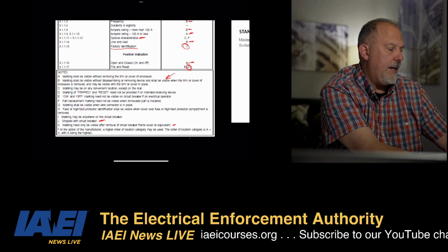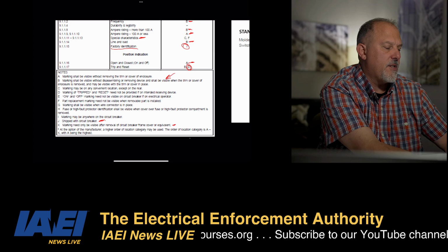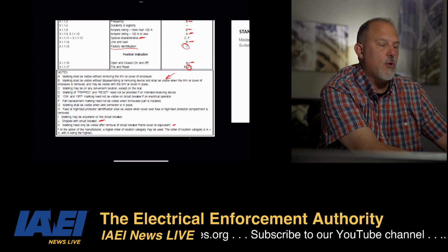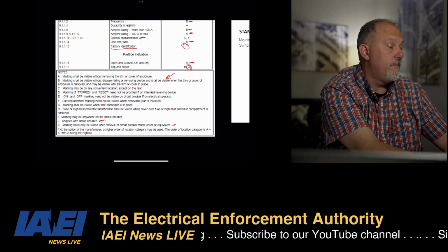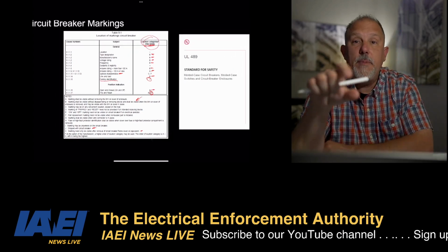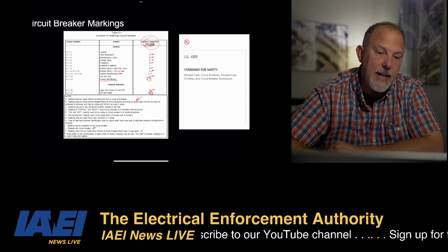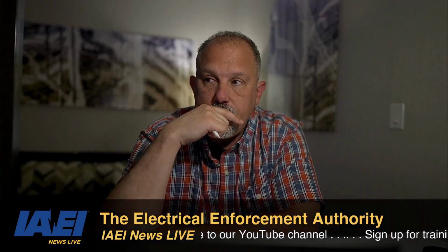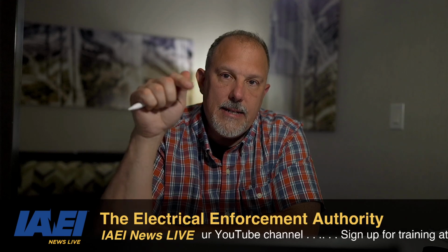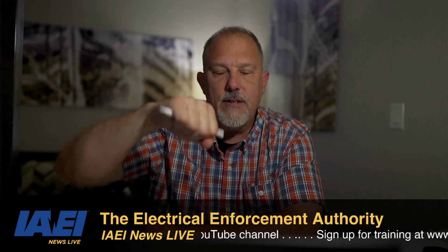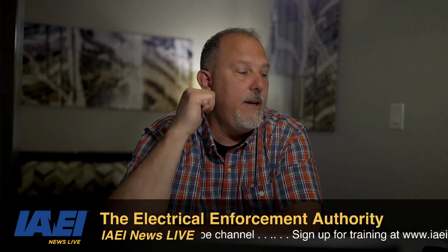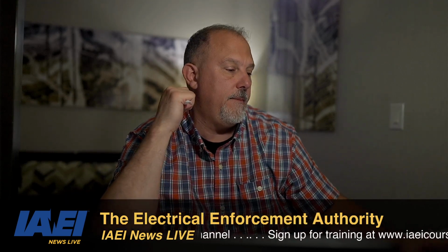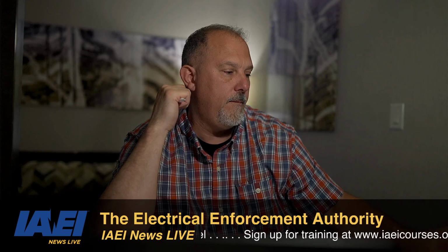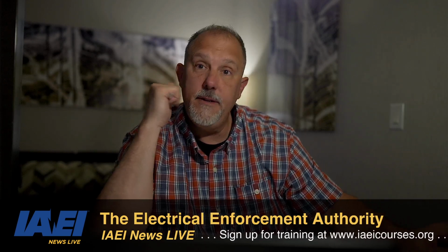Did I cover E? On, off marking need not be visible on circuit breaker if on electrical operator. What that means is, let's say you have a circuit breaker that is in an assembly and you have a handle on the outside that says on and off. That's what that provision gets you. Okay? Clear as mud? Getting better?